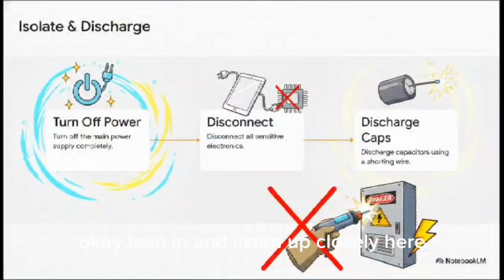Okay, lean in and listen up closely here, because this is, without a doubt, the single most critical part of this entire explainer. We are dealing with intentionally generated, extremely high voltage. So, strict safety protocols aren't optional. You absolutely must isolate and discharge your circuit completely before you begin. Step 1, you turn off the main power supply, period. Step 2, disconnect any sensitive electronics. Step 3, discharge any capacitors in the system using a shorting wire. I honestly cannot stress this rule enough. You must never, ever connect a Megger to a live, energized circuit.